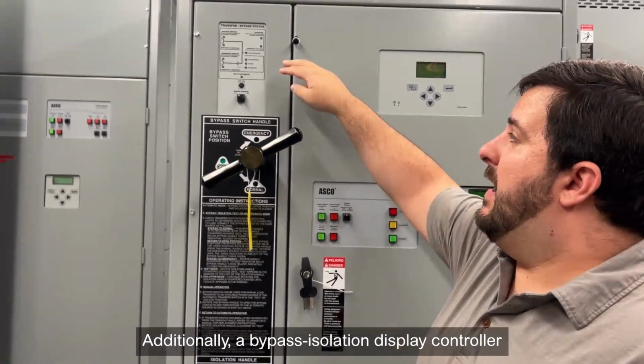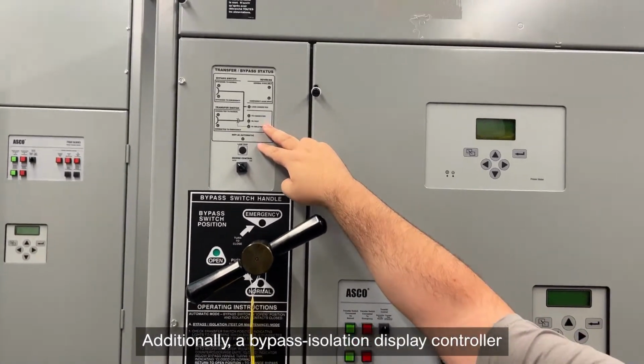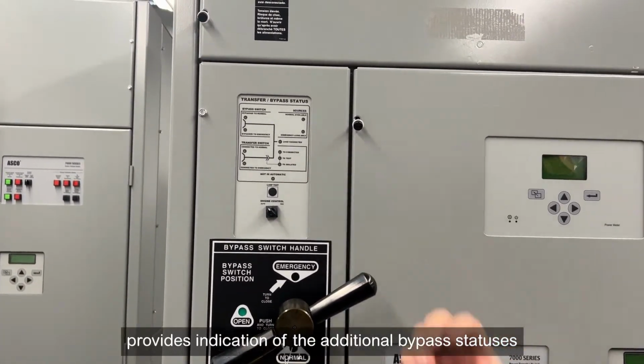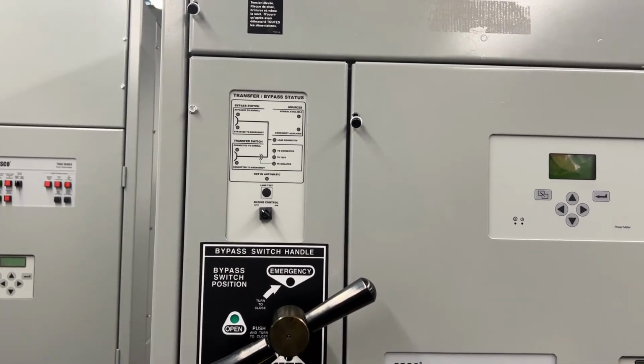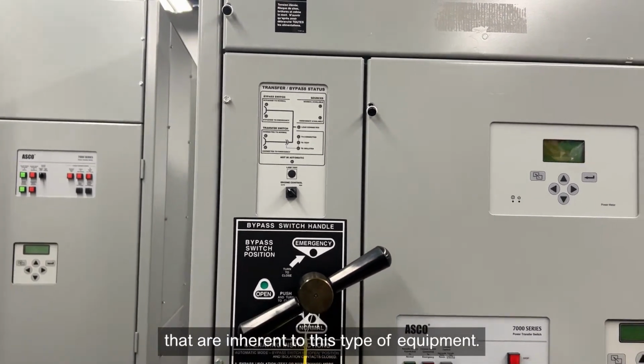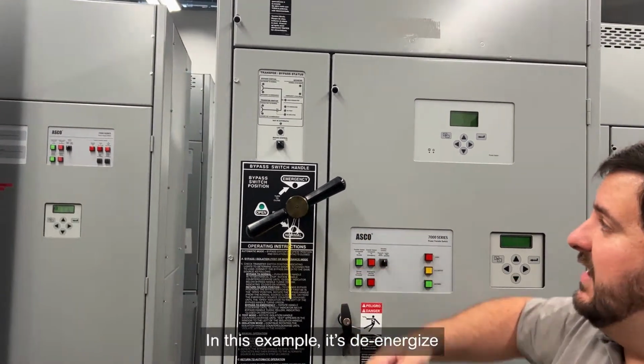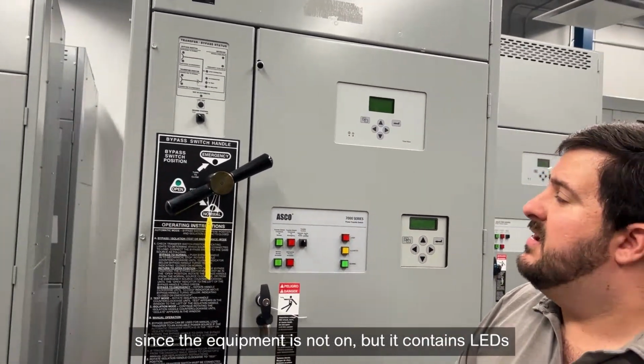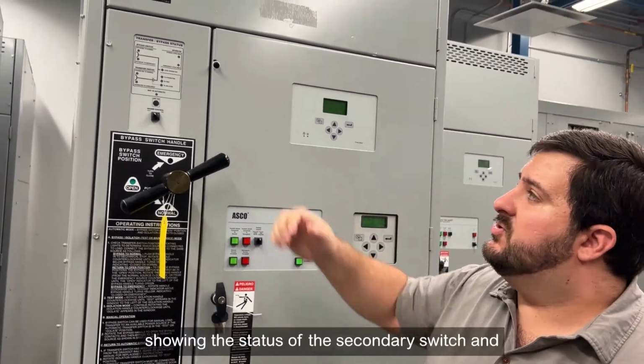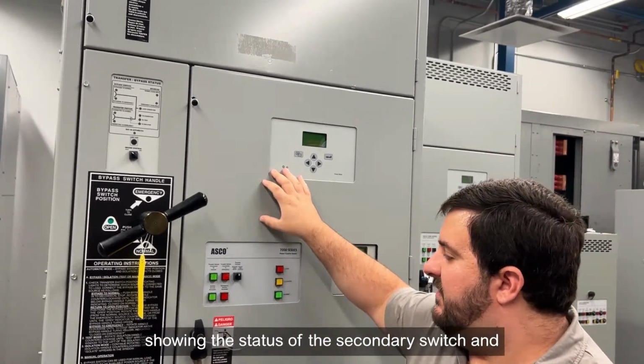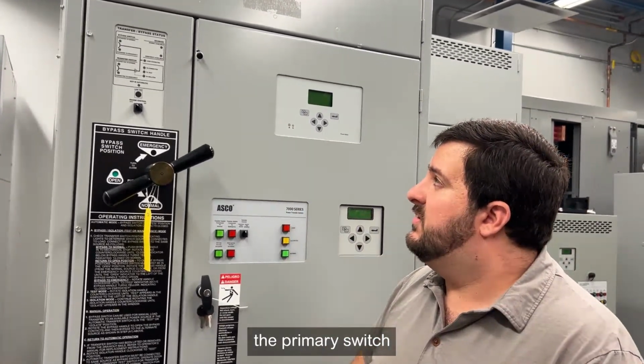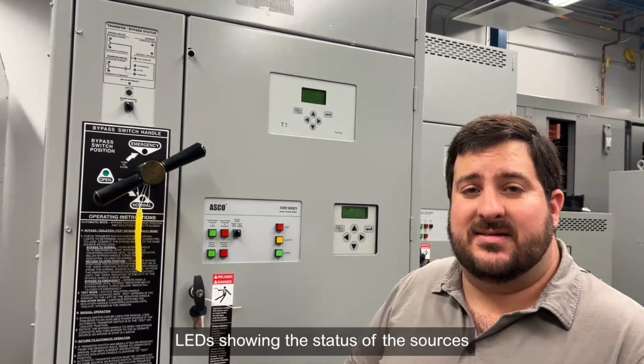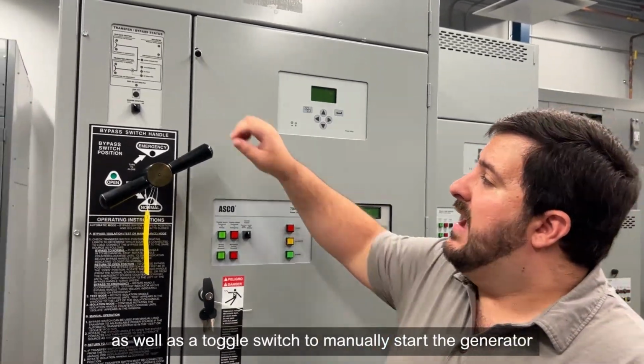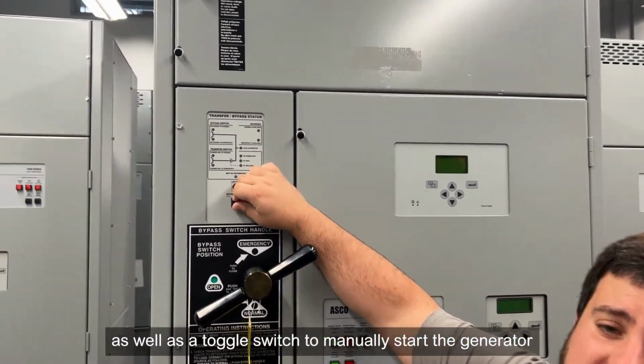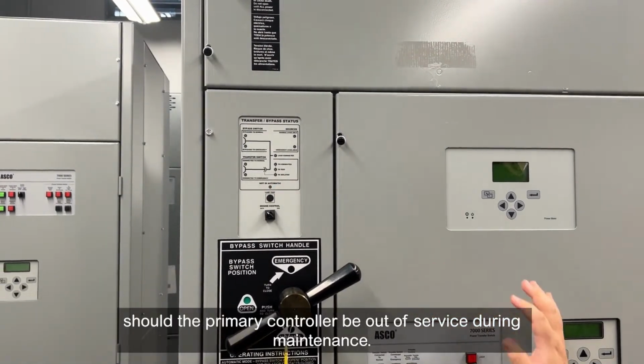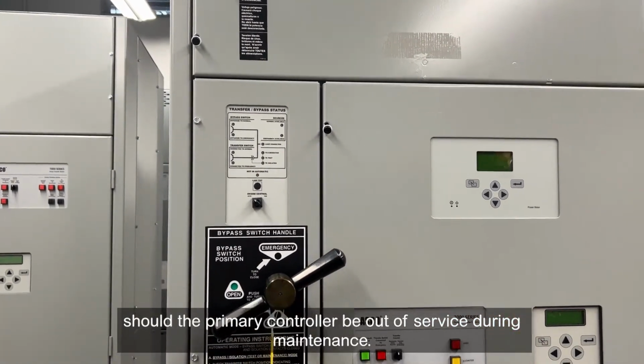Additionally, a bypass isolation display controller provides indication of the additional bypass statuses that are inherent to this type of equipment. In this example, it's de-energized since the equipment is not on, but it contains LEDs showing the status of the secondary switch and the primary switch, LEDs showing the status of the sources, as well as a toggle switch to manually start the generator should the primary controller be out of service during maintenance.